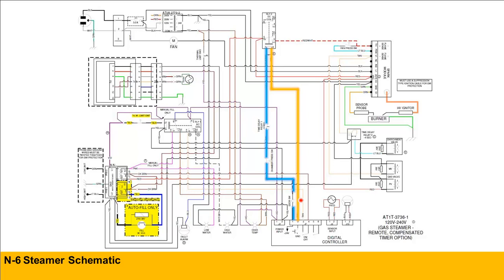The door handles, as far as the magnetic field, are made to work with this door switch. We've had situations where people have purchased non-OEM door handles and the magnetic field wasn't strong enough to actually close that switch. So once again, if you need a door handle, OEM, that's when you want to order that part from Parts Town. But for testing purposes, we're going to say the switch is good, so we jumped it, and still we have no call for heat. So our next stop is going to be our pressure switch. As Dan mentioned, it's a normally closed switch. The switch will open once the chamber pressure is at a half-inch water column. Easy enough test: we can test across the switch, or we can just go ahead and jump the switch.